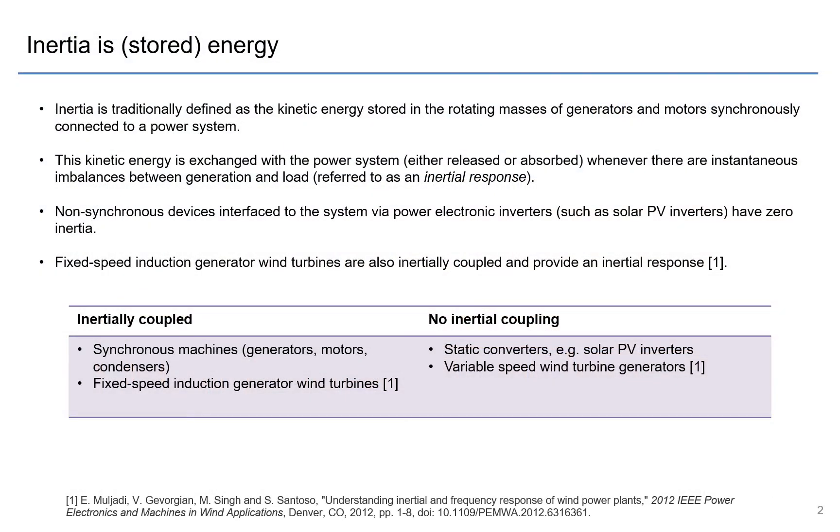At its core, inertia is energy, and more specifically it is the kinetic energy that's stored in the rotating masses of generators and motors synchronously connected to the power system. This kinetic energy is actually exchanged with the power system. It's either released or absorbed whenever there is an instantaneous mismatch between generation and load, and this is what we call an inertial response.